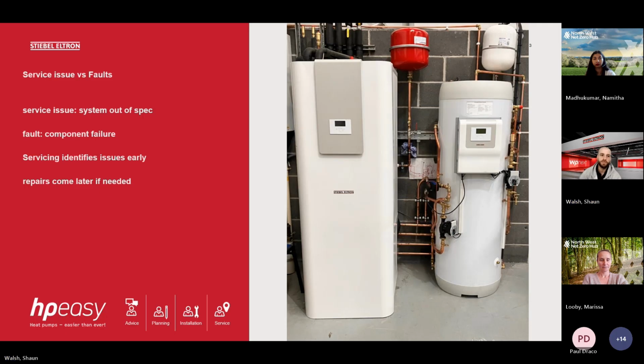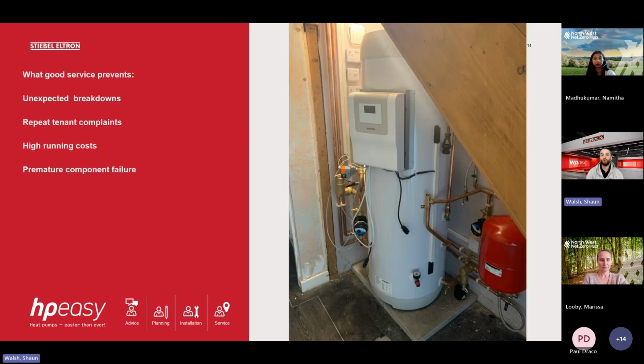Okay. So when we're looking at service, what a good service prevents is unexpected breakdowns of the machine, especially during the winter months when it can be very busy. During the winter months, air source heat pumps in particular are prone to what we call a defrost error. All the machines are designed to take care of themselves. If the evaporator on the back of the heat pump, where we're collecting the energy from, gets too cold, the machine is designed to pull heat from inside the property and send it into the heat pump, and it defrosts the machine. If there's not enough energy available in the property or in our buffer tanks, or not enough flow or temperature and things like that, that can cause us to have defrost issues.